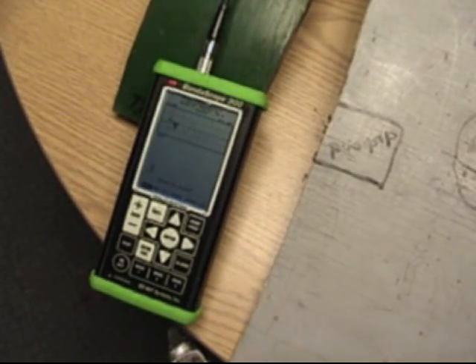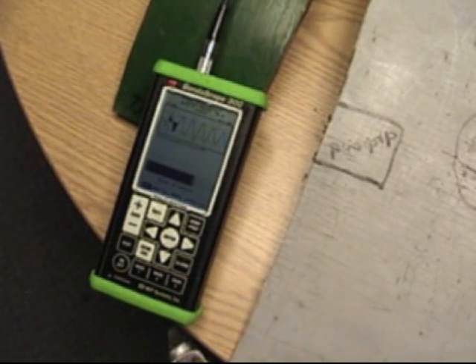Real easy to use. We're looking at either amplitude or phase or a combination of both. The two samples that you sent me we got the best response from amplitude. This standard here that I just showed you, the sample's best response was coming from phase so I set the sweep to show phase. On yours I showed it to show amplitude. The alarm was set for response for the phase on this one. On yours it was amplitude but it didn't take very long.